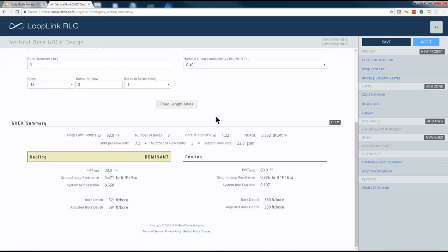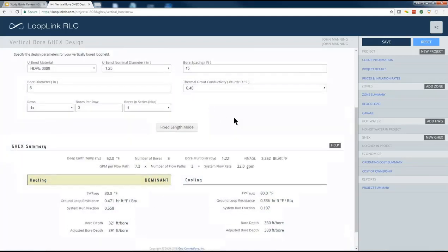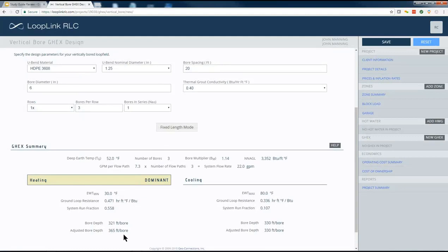So one thing that you can do, and I just want to point this out, that has a minor impact, it has a much bigger impact in poorer soils, especially in the south where it's cooling dominant and you dump a lot more heat than you extract. But one thing that you can do to offset or counteract ground load imbalance is simply space your bores out. So by going from a 15 to a 20-foot spacing, you can see my bore length dropped from the 390 feet to 365 feet per bore, times 3 bores.